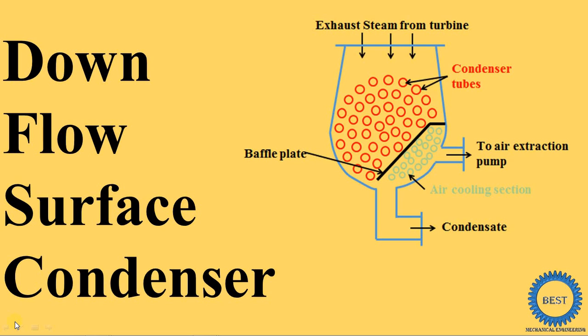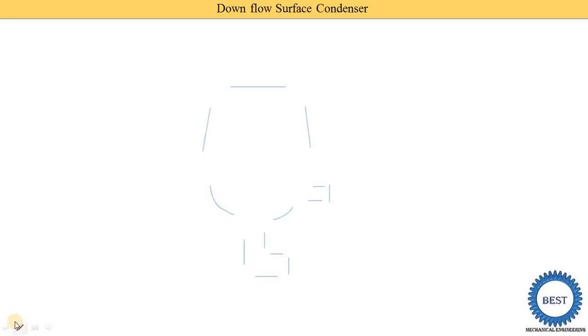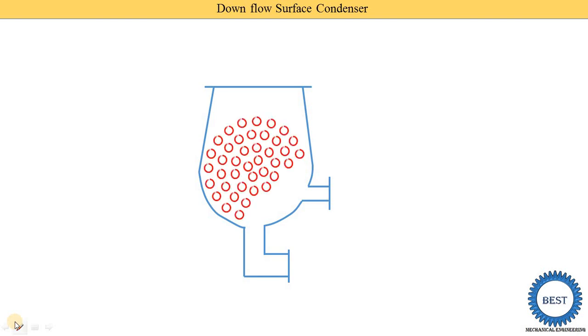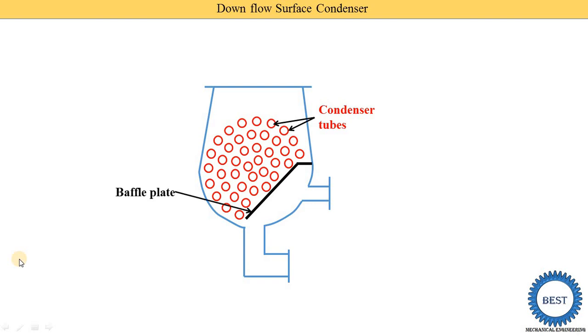Now we understand the construction of the downflow surface condenser. This is the outer part. Inside the condenser there are a number of tubes, and these tubes are divided into two parts. The red color tubes have larger diameters. Another section is created below, separated by baffle plates. Below the baffle plates there are more tubes but with a smaller diameter.